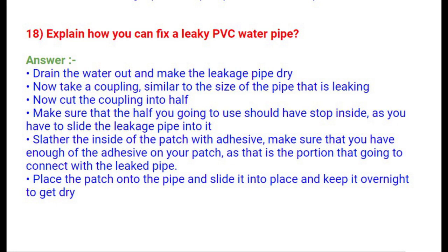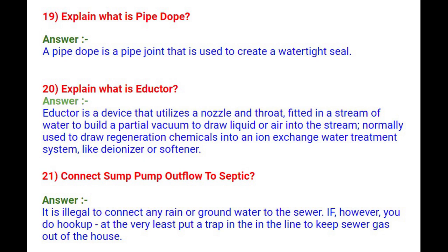Question 19: What is pipe dope? A pipe dope is a pipe joint compound used to create a watertight seal. Question 20: What is an eductor? An eductor is a device that uses a nozzle and throat fitted in a stream of water to build a partial vacuum to draw liquid or air into the stream, normally used to draw regeneration chemicals into an ion-exchange water treatment system, like a deionizer or softener.